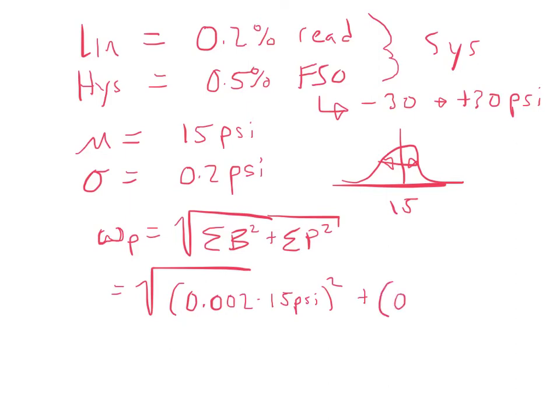Plus our second bias error, which is our hysteresis. So, that's 0.5%, so 0.005 times the full-scale output. Our full-scale output can go between minus 30 and positive 30. So, that's a range of 60 psi. So, we're going to multiply that by 60 psi and square it. And that gives us our sum of our Bs. Now, we need to sum our Ps all under this radical. So, we're going to add plus our sigma.